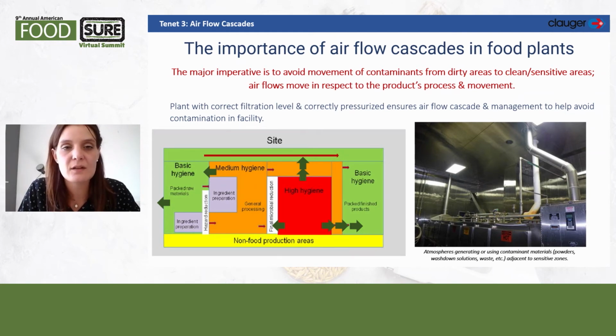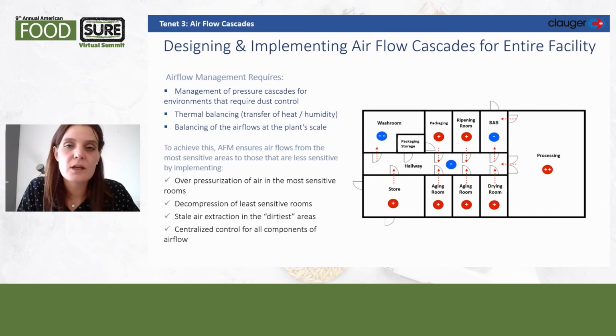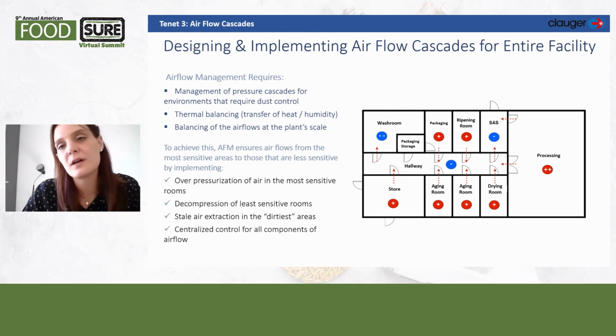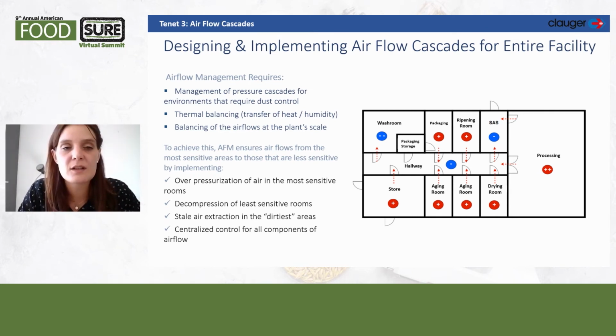So you can see on the left the map with the different sensitive zones, and you have to have the airflow from the most sensitive zone to the less sensitive zones. So here is an example of how we implement airflow cascade for an entire facility. The overpressurization is on the most sensitive room, such as processing here, and the depressurization is in the less sensitive room, such as the washroom. This is in order to avoid a spread of dirty air in your company.